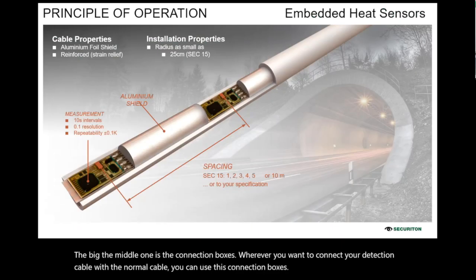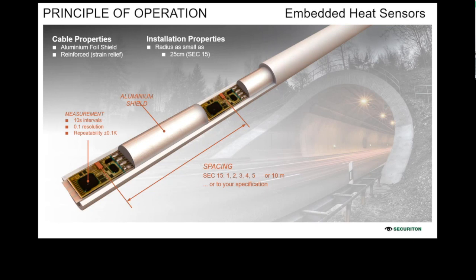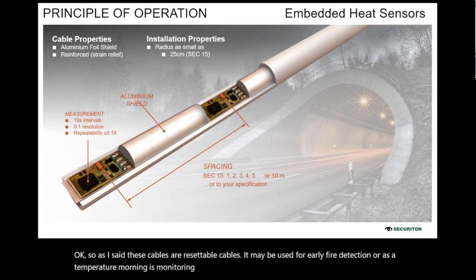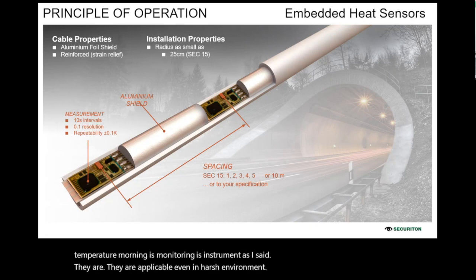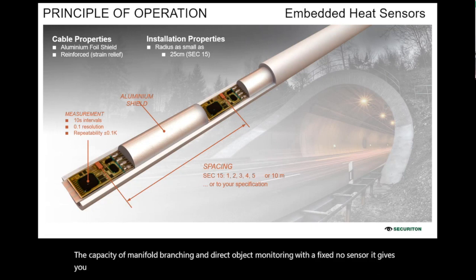Okay, so as I said, these cables are resettable cables. They may be used for early fire detection or as a temperature monitoring instrument. As I said, they are applicable even in harsh environments. The capacity of manifold branching and direct object monitoring with a fixed sensor gives you the strength to use these cables in any kind of environment, any kind of application.